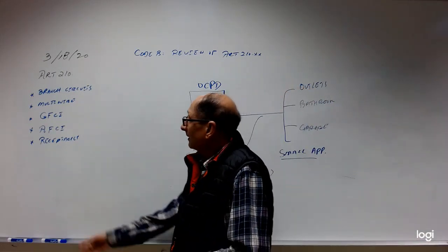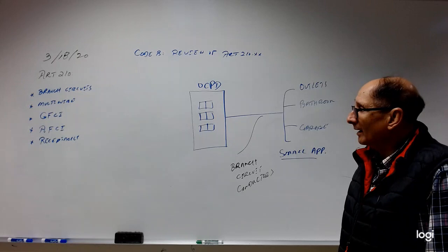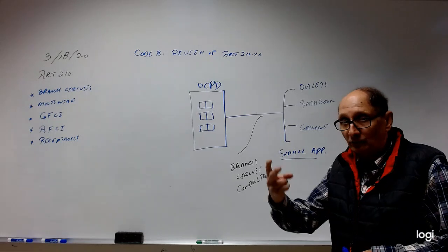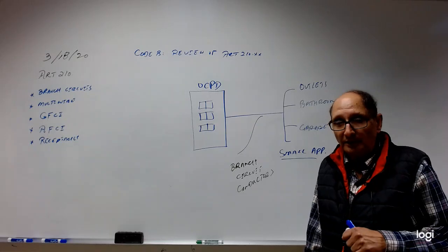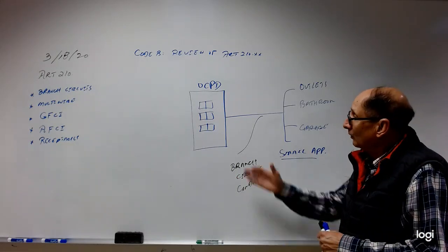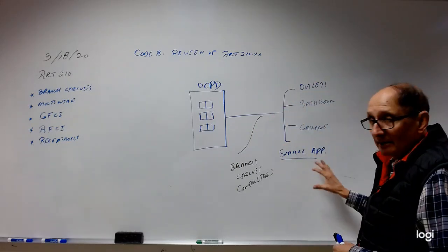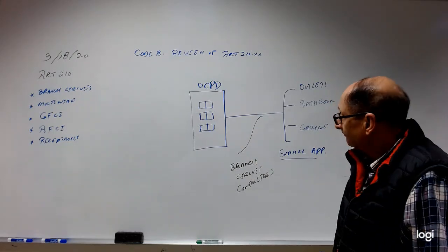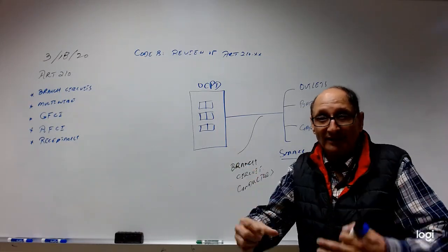The next one is, of course, the multi-wire branch circuit. So what is a multi-wire branch circuit? Based on the requirements, a multi-wire branch circuit has two or more ungrounded conductors that share a neutral. And the multi-wire branch circuit must originate from the same panel board, which in this case is our panel board or our breaker. So these branch circuits that are going to share resources from this part must originate from the same panel. They must have the same one disconnecting means.